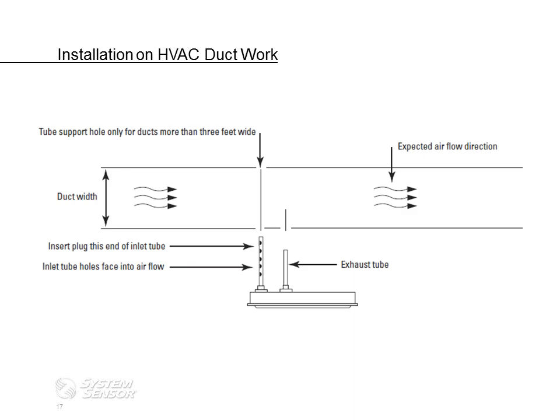This diagram just shows an installation of a typical duct detector in standard ductwork. It just, for illustration purposes, shows you the duct width, the direction of the airflow, where the sampling tube is mounted, and the way that the sampling holes are faced into the airstream exhaust tube.